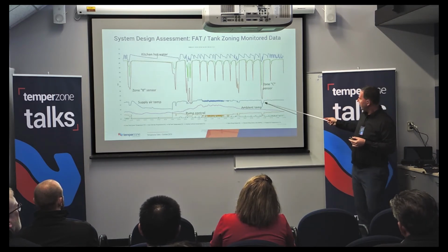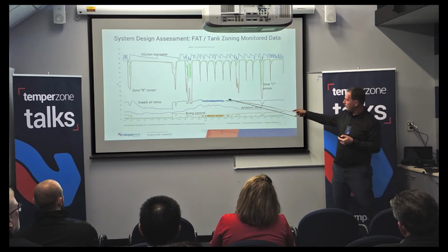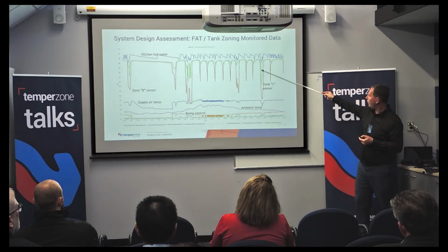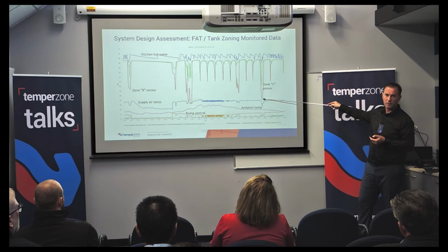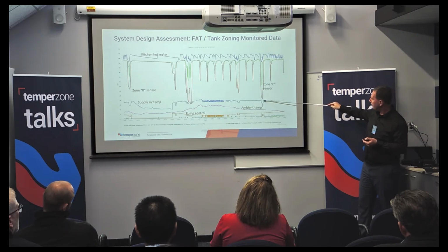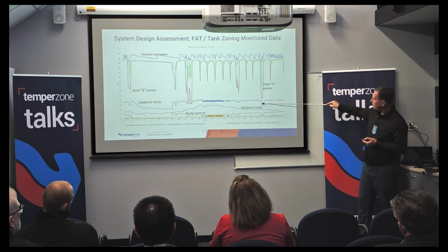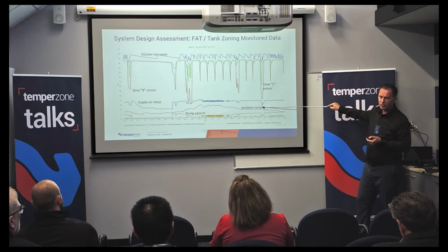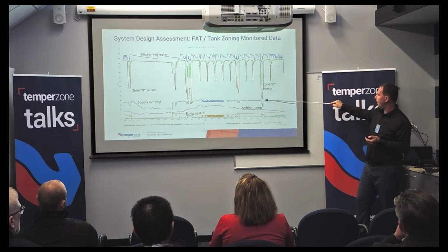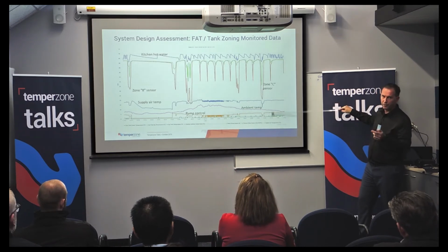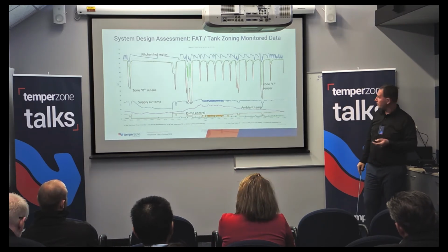And you can see here how the supply air temperature is being controlled, and when they've drawn off a whole bunch of water to defrost chicken, you can see that the pump's gone to minimum speed, and then for a very short time it's turned off altogether, and then it's gone back to minimum speed, and it's quickly recovered again back to full efficient temperatures.